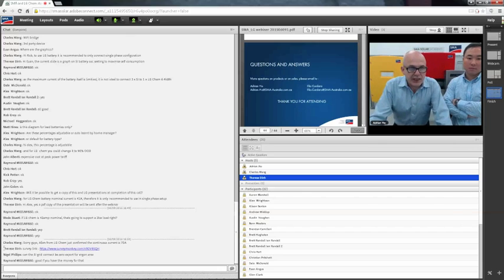The second question: if LG Chem is 42 amp nominal, that's going to support a 2 kilowatt load, right? As far as I understand, the 42 amp is the ideal amp, but it can actually do 70 amp continuous - is that correct? That's correct. And what does that mean in terms of how many kilowatt hours it can provide from a peak point of view?